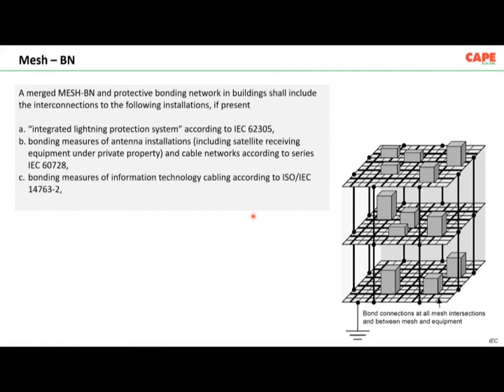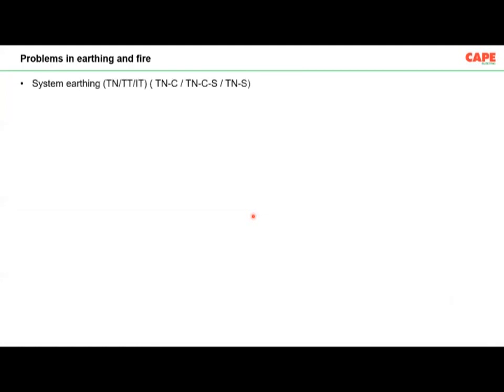Modern buildings also require, in addition to the global earthing system, they are also supposed to have a mesh bonding network. Mesh bonding network means the structural steel elements are interconnected in such a way that the resistances between the installed equipment are very much reduced. As a result, you achieve a very high degree of safety, a very high degree of reliability in your electronic equipment. Actually, earthing is all about these things.